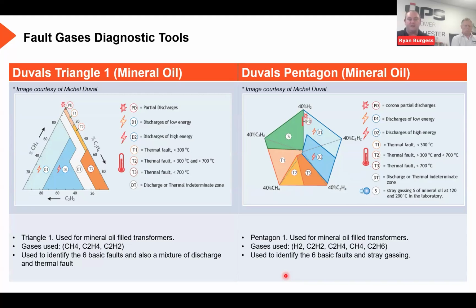So, interpreting the faults from that test and what they mean. There are many different models that can be used to interpret your data. Here at VPS, we use predominantly Duval's triangle and Duval's pentagon. But no matter what tool you're using, the basic principles are the same. So hydrogen is typically the first gas to appear when there's a fault, which is an early indicator of faults such as partial discharges, low energy arcing, and a non-fault phenomenon known as stray gassing.